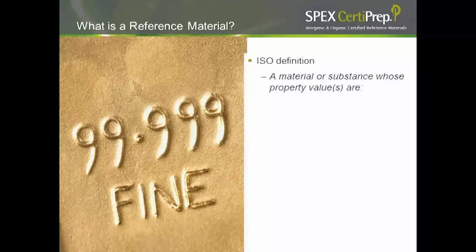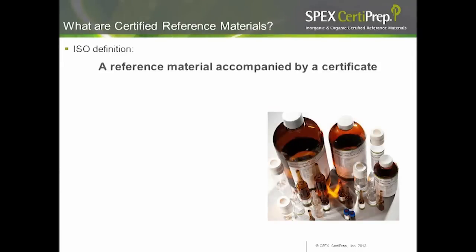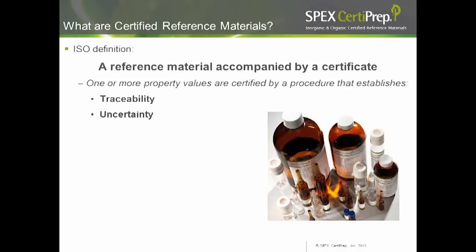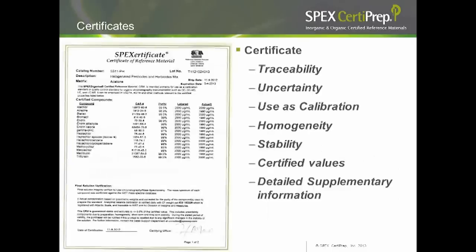A reference material is a material or substance whose property values are sufficiently homogeneous and well established, used for calibration of an apparatus, assessment of a measurement method, or to assign values to materials. A certified reference material is a reference material accompanied by a certificate. This certificate must contain certain necessary information according to ISO guidelines, including property values such as traceability and uncertainty, as well as supplementary information including certified bodies, methods of measurement, how the material is prepared, and statistical treatment of results. Our certificates include uncertainty, traceability, how to use the standard for calibration, storage information, and intended use.